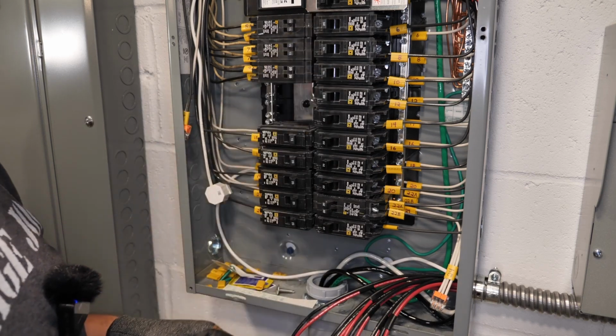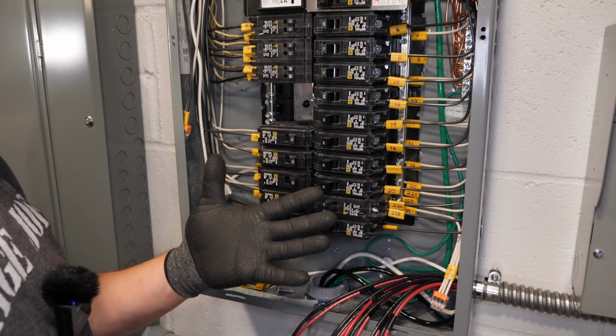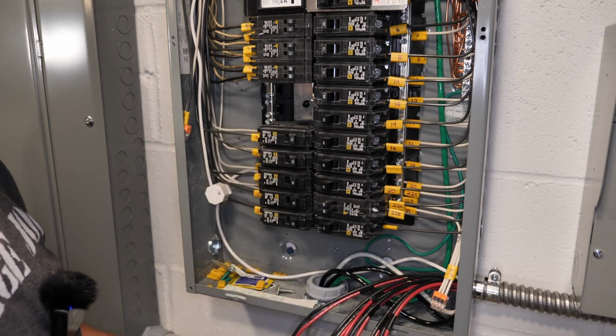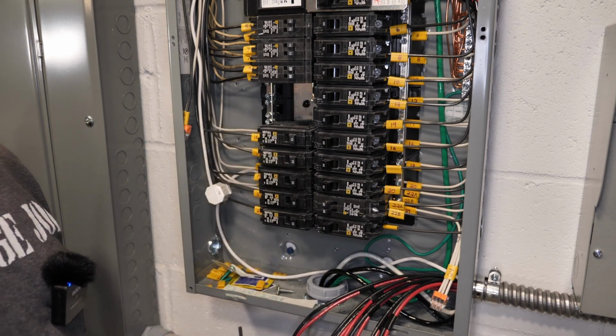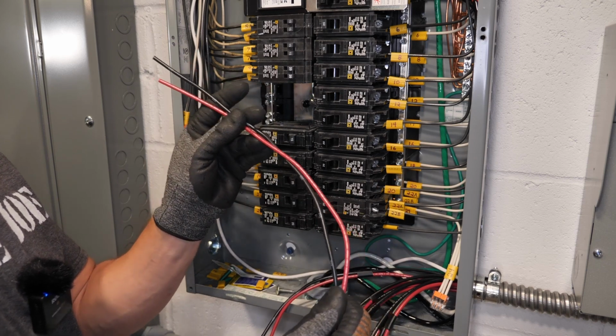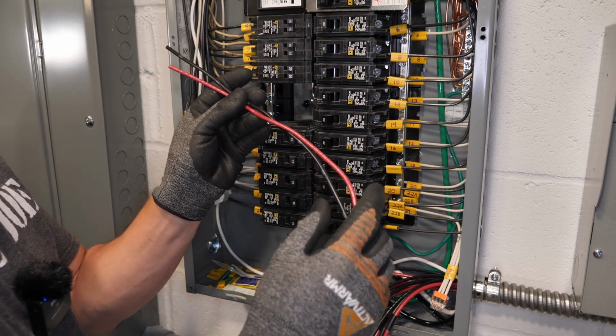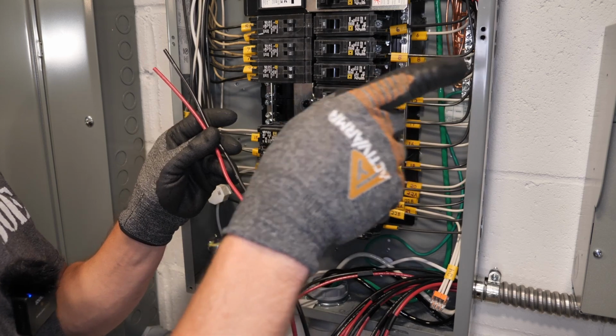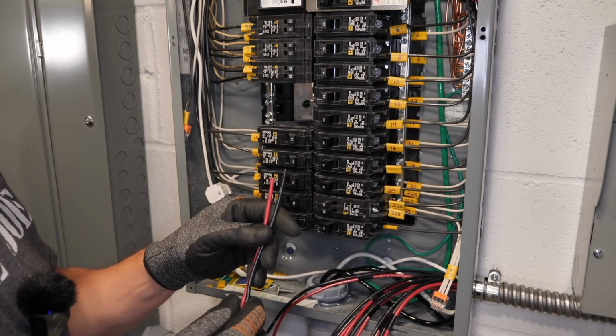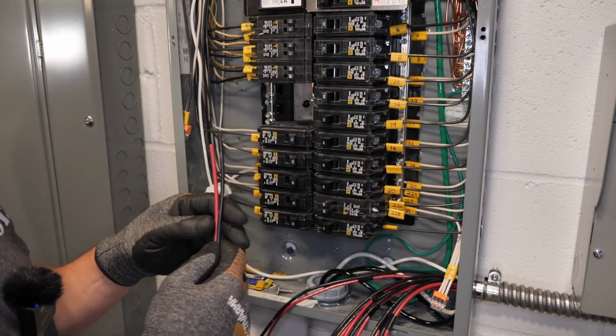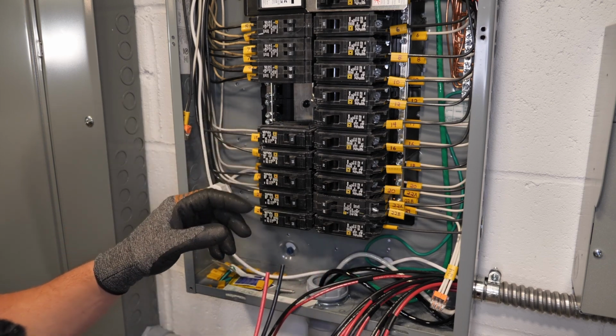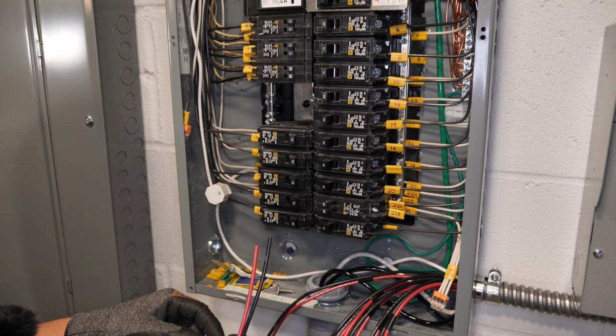All the 120 volt circuits are going to be exactly the same, however it's just going to be one circuit breaker. So what you need to do next is grab a matched pair. This one is letter E, so that's going to be circuit breaker E on the critical loads panel. We're going to do the exact same thing, so find your device or room you'd like to power and let's get that wired up.